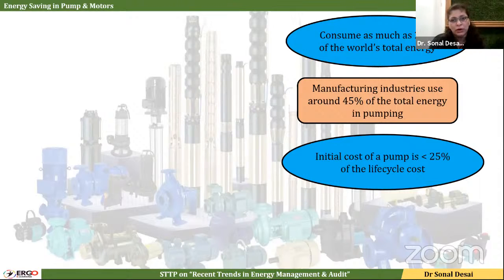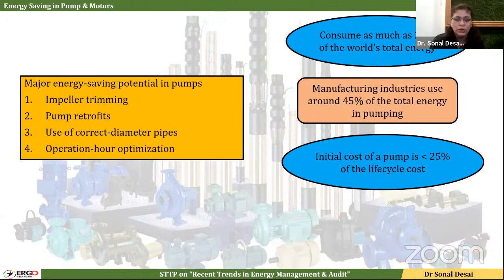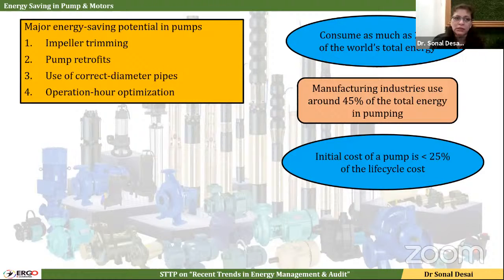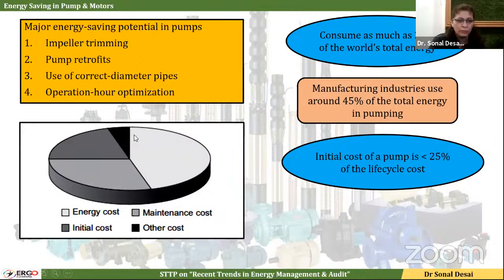Also, these are a matter of concern because when we compare initial cost and running cost or life cycle cost, the initial cost of the pump is very, very low compared to the life cycle cost. So it is always better that we select the system initially in such a way that the running cost is optimized and the overall life cycle cost is reduced. When I talk about energy saving potentials, we will be discussing impeller trimming, how to retrofit pumps, what the correct diameter of piping is so that it can reduce the burden on pumping load, and how to optimize operation hours.